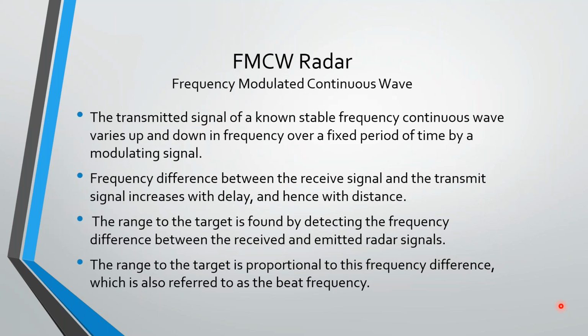That brings us to the other method of doing non-contact radar, and that is FMCW, or frequency modulated continuous wave. Just as the name implies, we continuously send signals and we modulate the frequency within a range. The wider that shift in range is, the better we're able to more accurately determine the level.